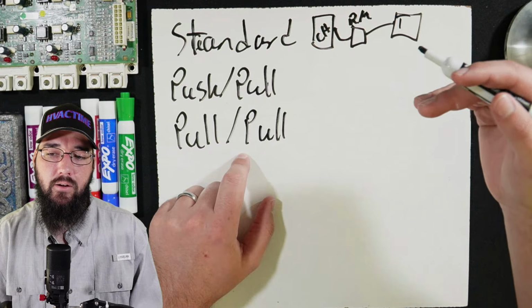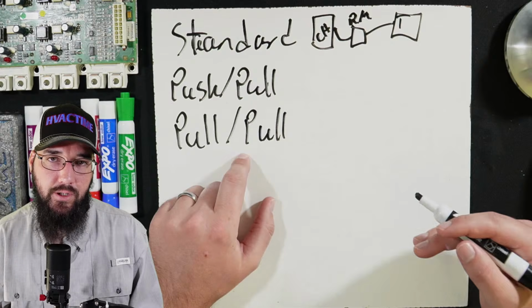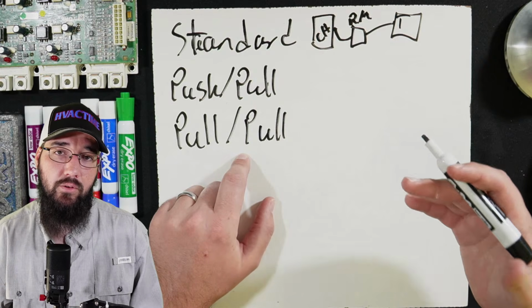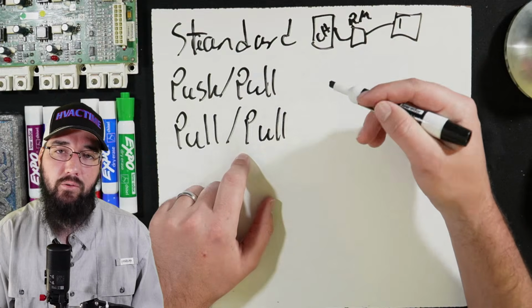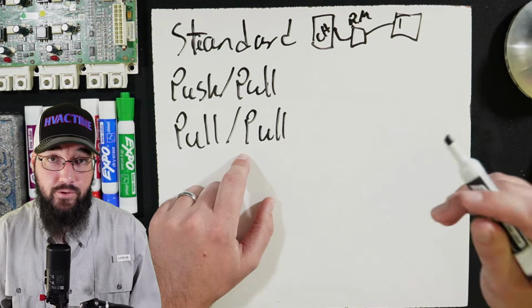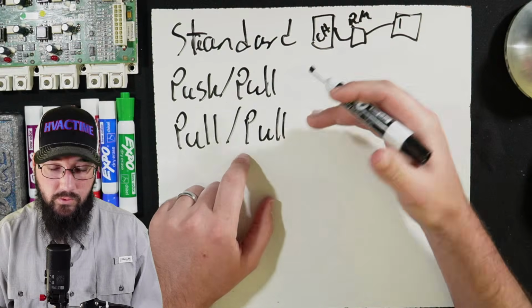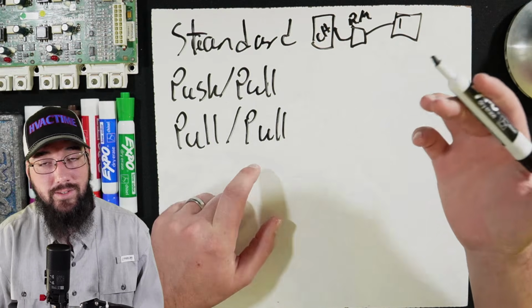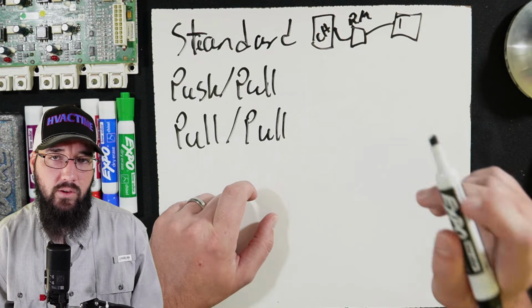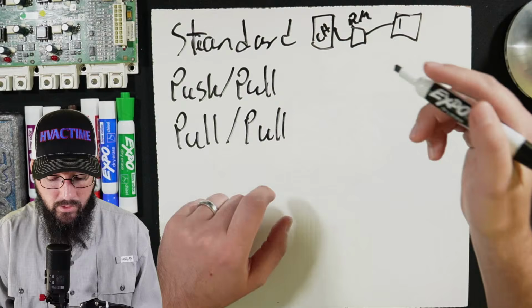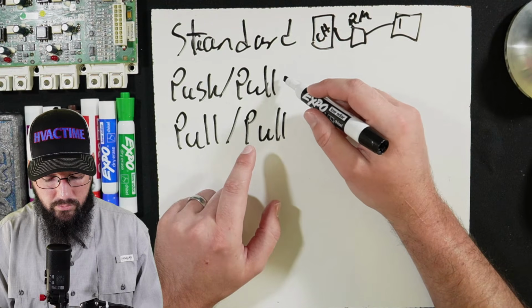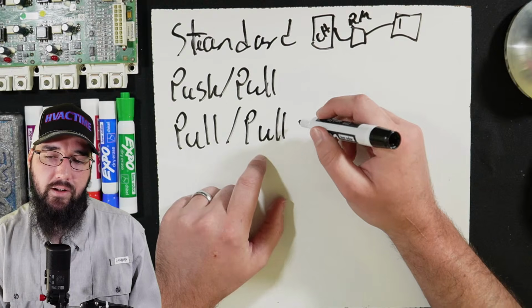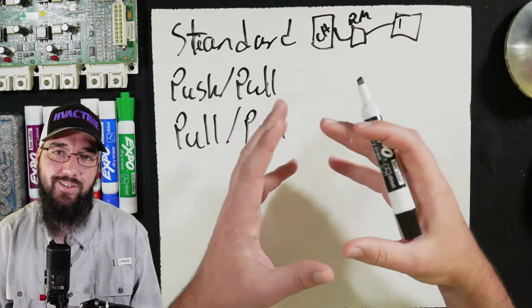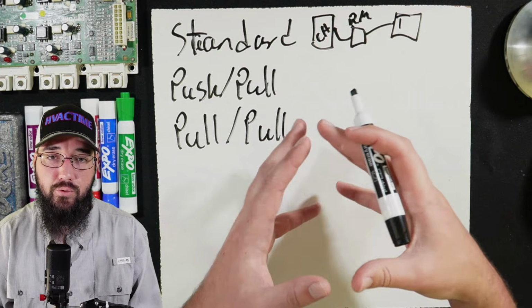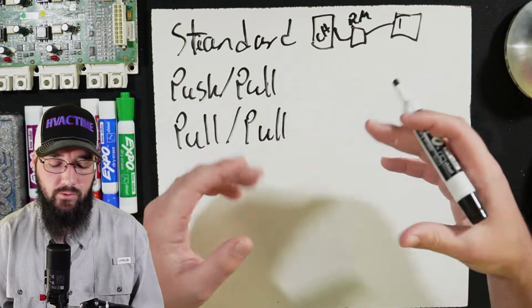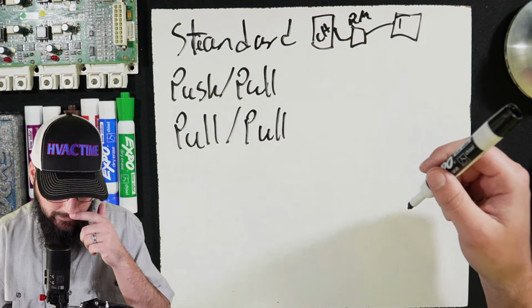Now, push-pull and pull-pull are a more rapid way of getting our liquid refrigerant out of the machine very quickly, because that's where most of your time is going to be killed. If you're doing a standard recovery, you're trying to boil out the entire refrigerant charge on the system, which takes absolutely forever, but sadly, especially on a lot of air-cooled lines, is necessary. So push-pull and pull-pull are only effective when you actually have the liquid refrigerant consolidated into a central place inside the system, which depends on the evaporator, and I'll explain that in just a second.